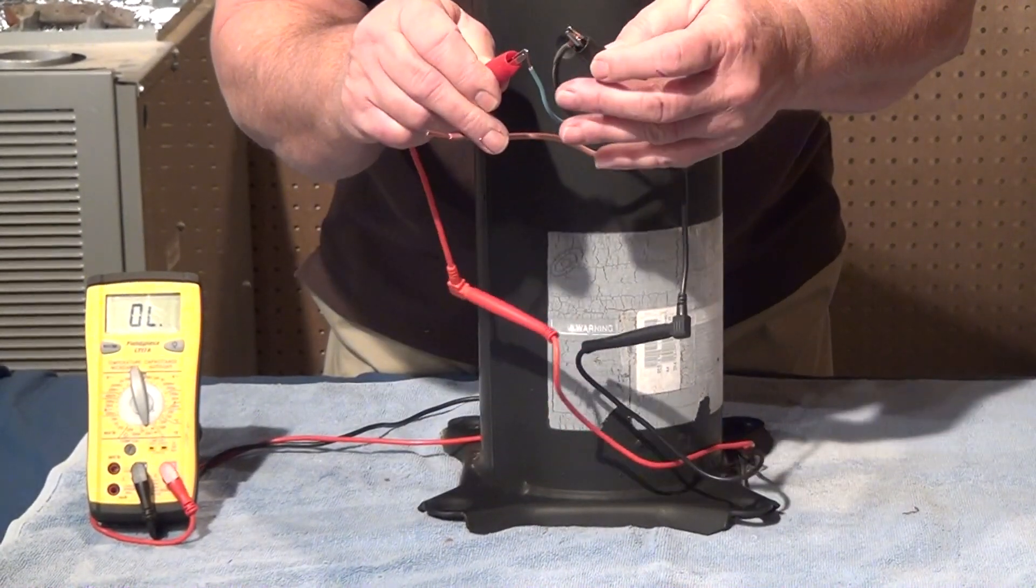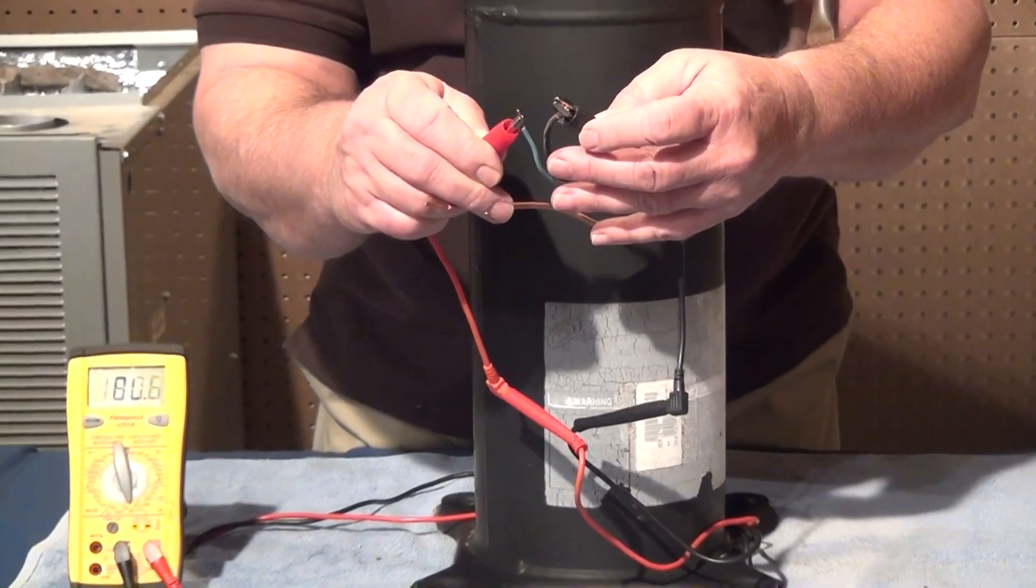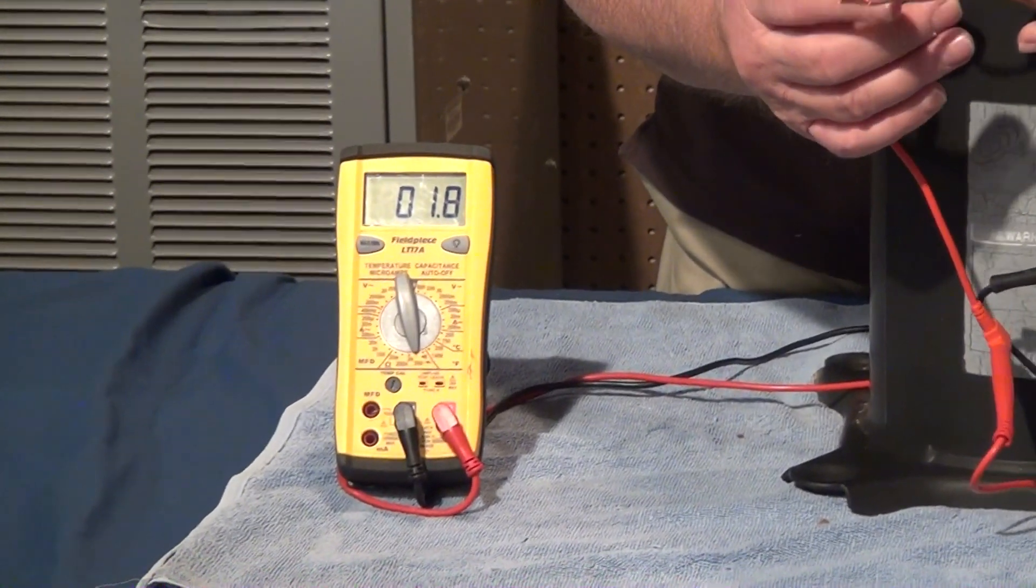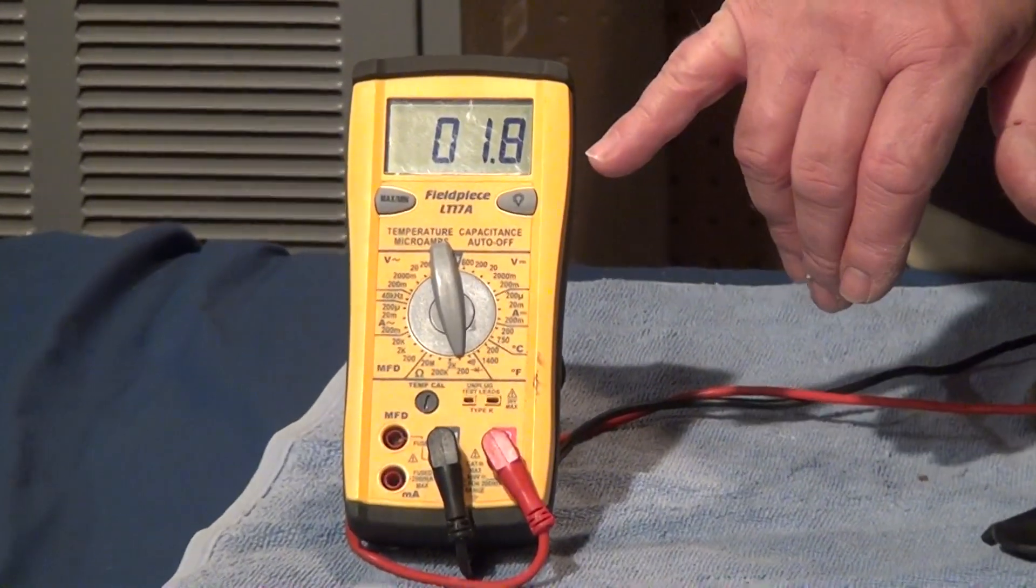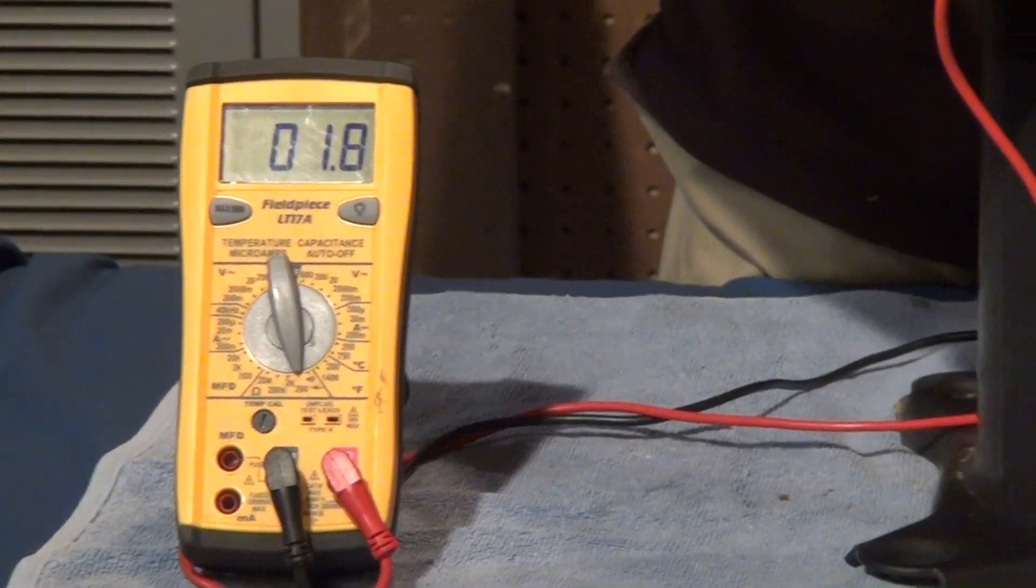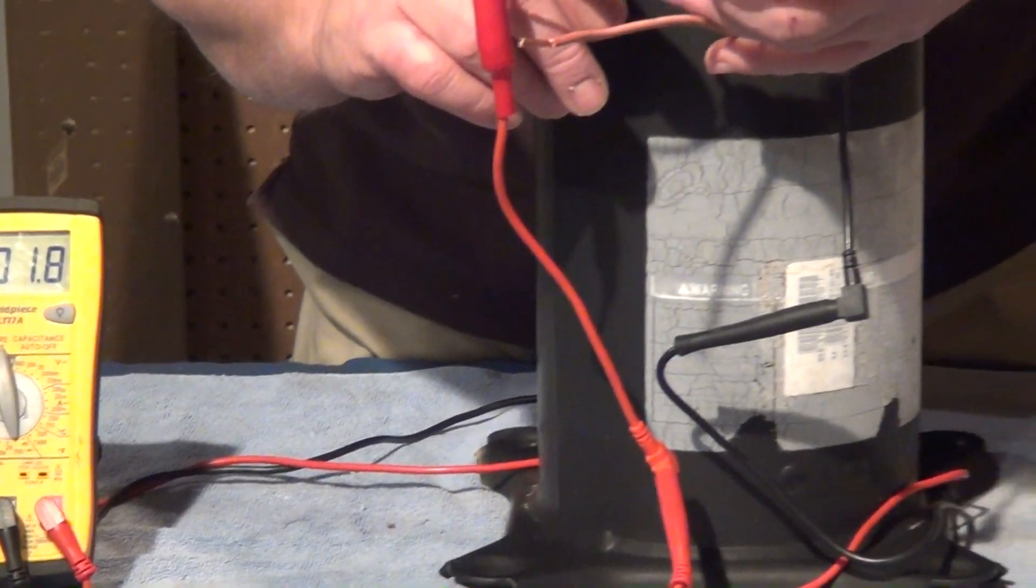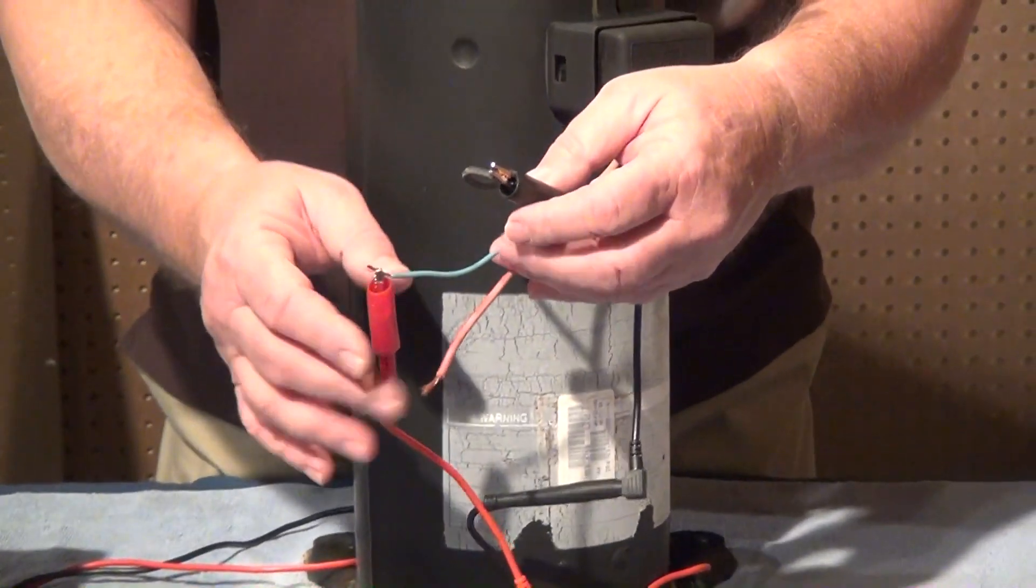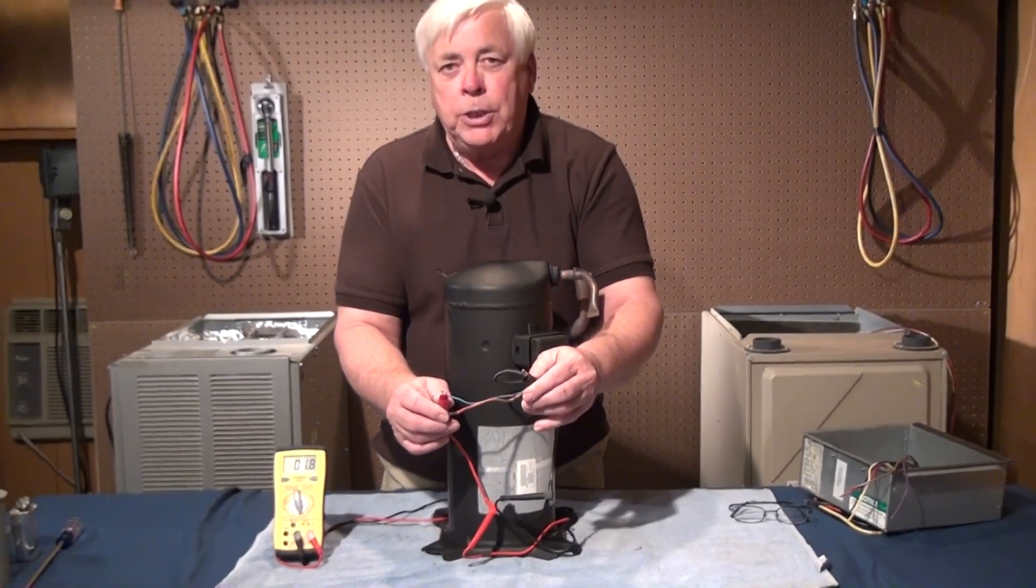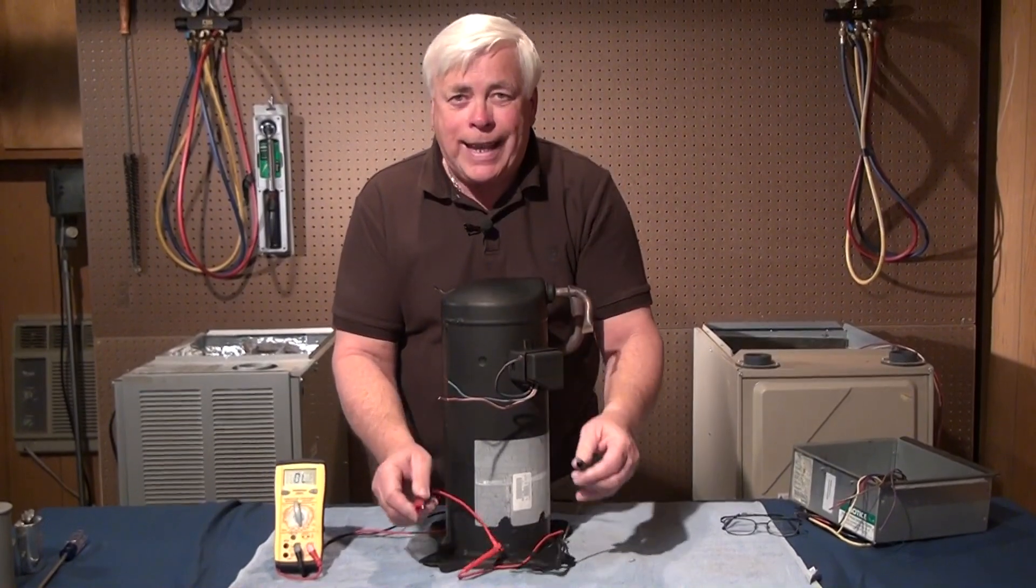When we move over to test this particular winding though, what you can see is we're going to have a different resistance reading. The resistance reading that we're going to get on our meter for this particular test is going to be just shy of two ohms resistance, which means we are in fact testing the start winding of the compressor. So the bottom line on testing the compressor is very simple. We've done the electrical tests and we know that the compressor is okay electrically.